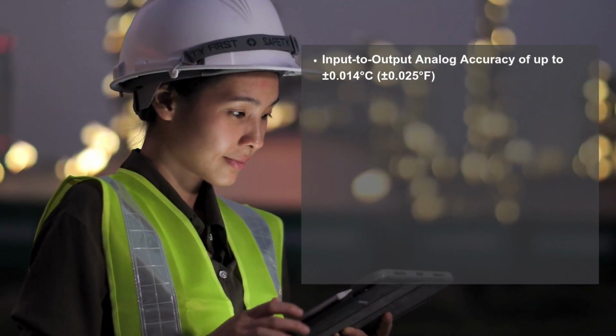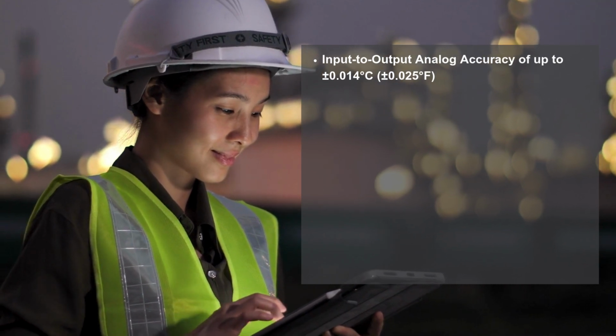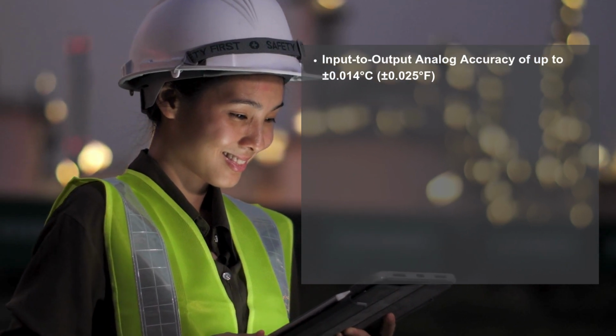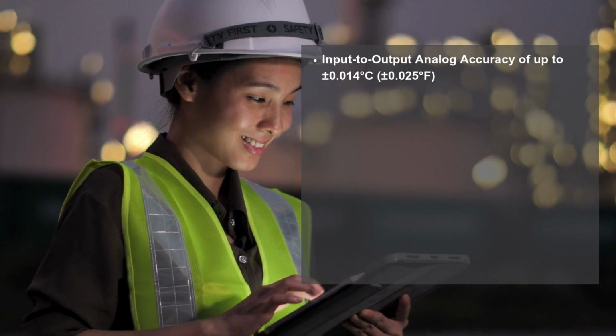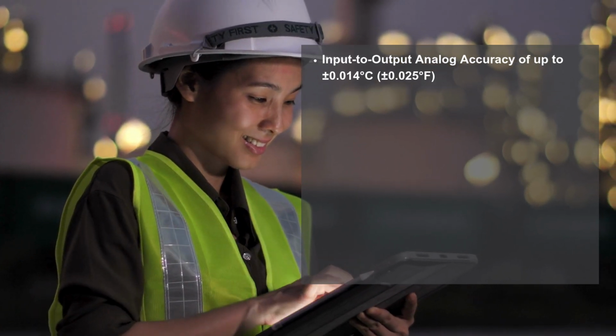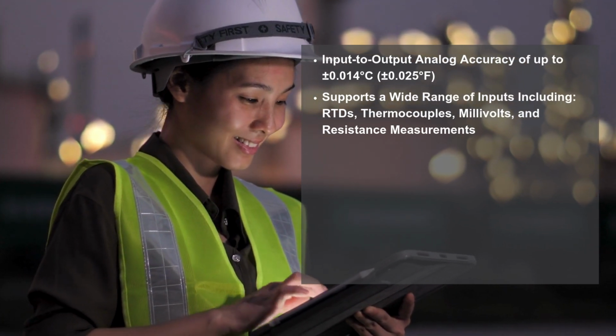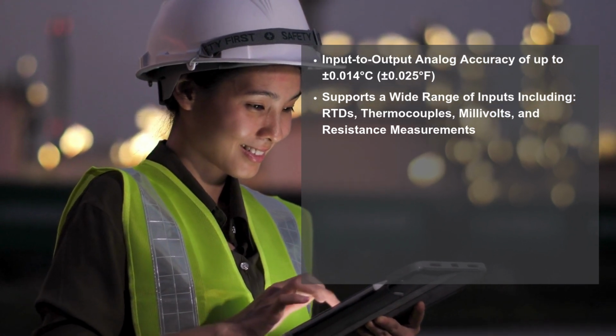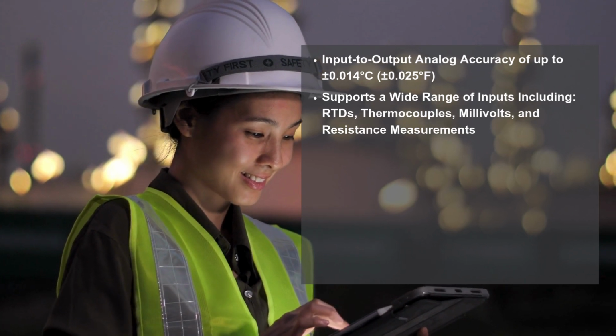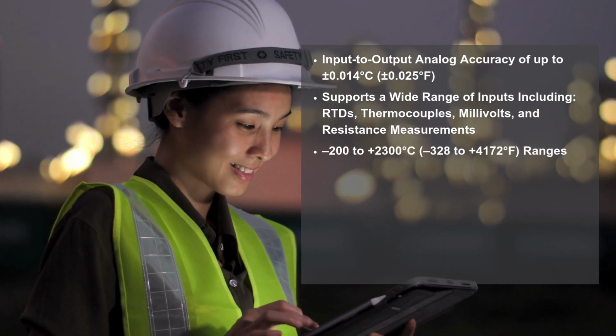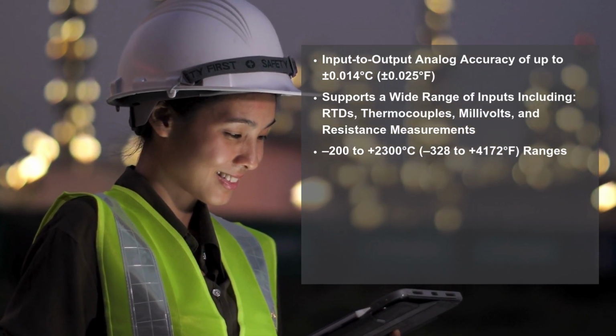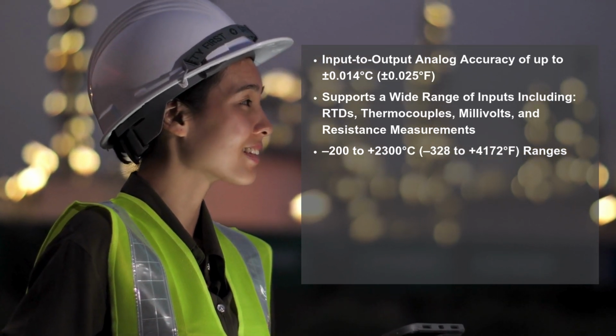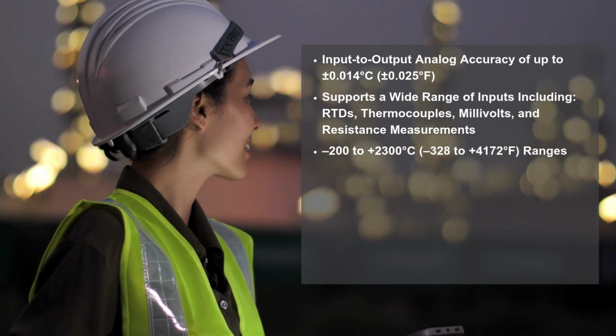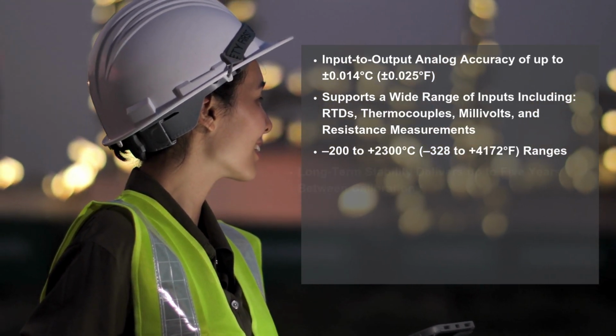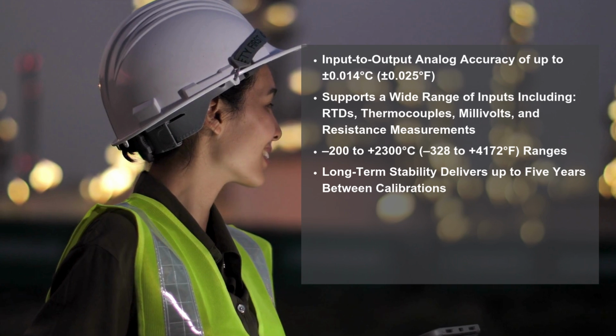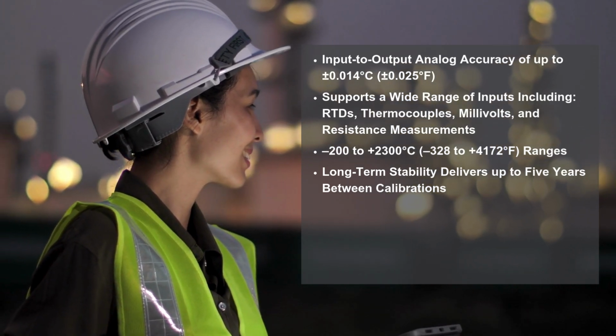With input to output analog accuracy of up to plus or minus 0.014 degrees Celsius or plus or minus 0.025 degrees Fahrenheit, our solutions deliver the absolute best precision in the industry. They support a wide range of inputs, including 2, 3, and 4-wire RTDs, thermocouples like J, K, and R types, millivolt signals, and resistance measurements. Our devices operate seamlessly across extensive temperature ranges from minus 200 to plus 2,300 degrees Celsius, or minus 328 to plus 4,172 degrees Fahrenheit. Long-term stability ensures up to 5 years between calibrations, minimizing downtime and maintenance.